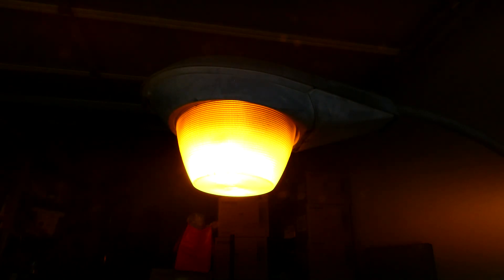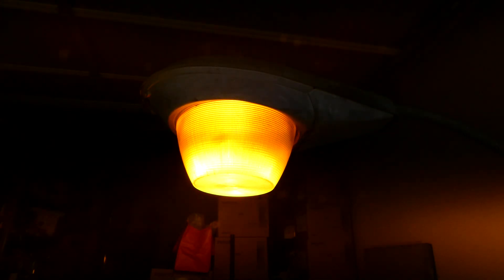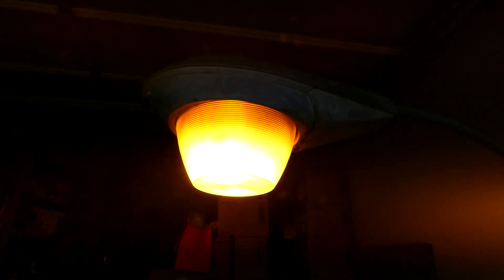Similar to my metal halide retrofit lamps, which are 330 watt — while they are lower wattage, they're still much brighter than standard mercury lamps would be. They're not made to retrofit mercury vapor specifically, but any metal halide mercury ballast can run them anyway, so they could be interchanged.